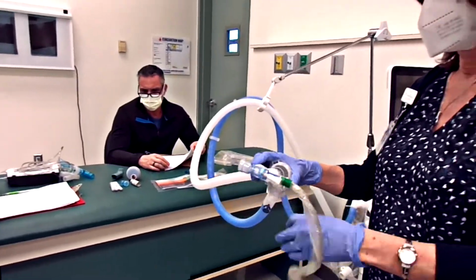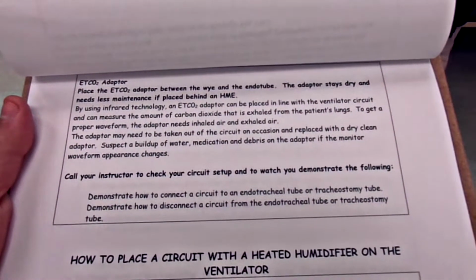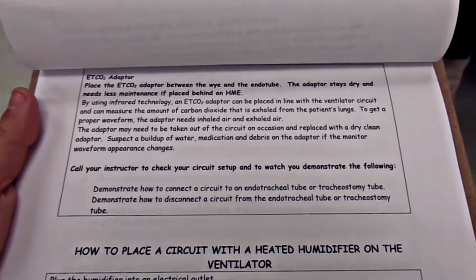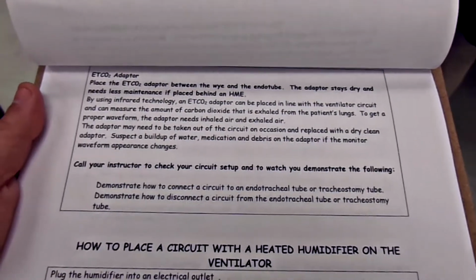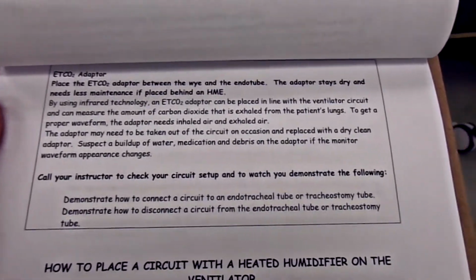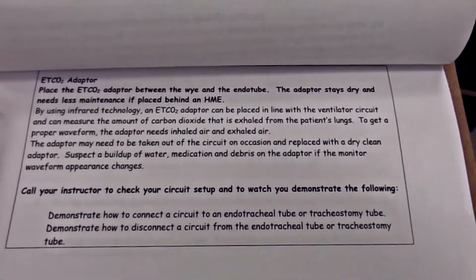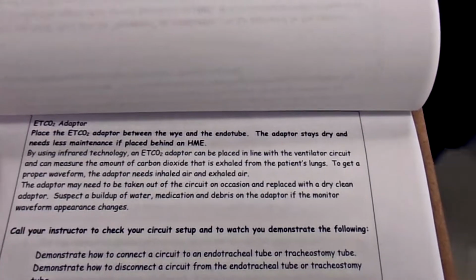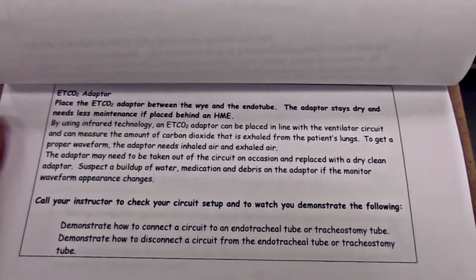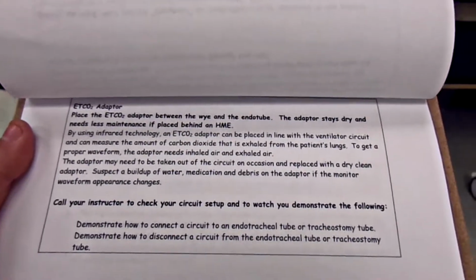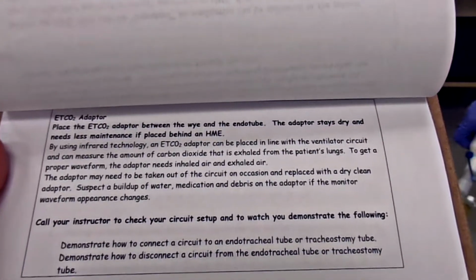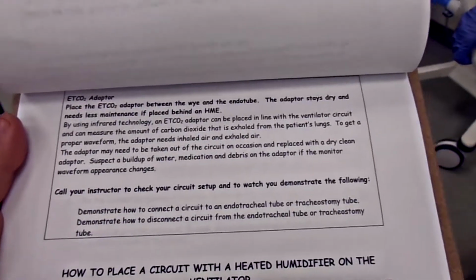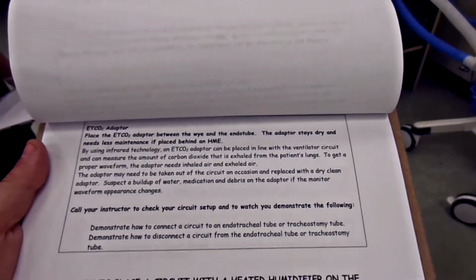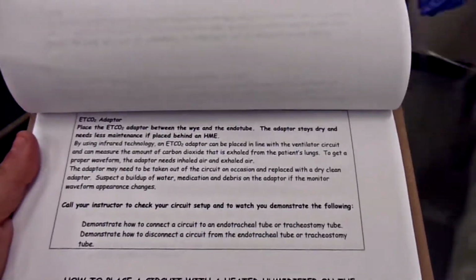Okay, what's next? ETCO2 adapter. Place the ETCO2 adapter between the Y and the endotube. The adapter stays dry and needs less maintenance if placed behind an HME. By using infrared technology, an ETCO2 adapter can be placed in line with the ventilator circuit and can measure the amount of carbon dioxide that is exhaled from the patient's lungs. To get a proper waveform, the adapter needs inhaled air and exhaled air. The adapter may need to be taken out of the circuit on occasion and replaced with a dry, clean adapter. Suspect a buildup of water, medication, and debris on the adapter if the monitor waveform appearance changes. Call your instructor to check your setup.